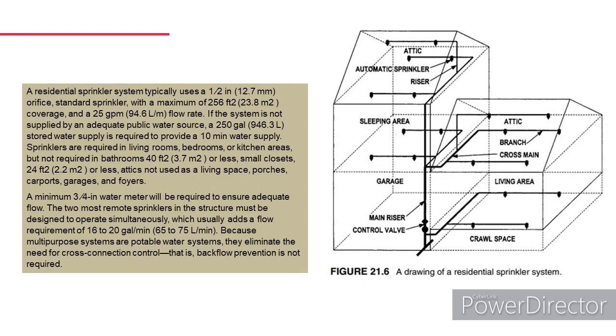A residential sprinkler system typically uses a 1/2 in, 12.7 mm, orifice, standard sprinkler, with a maximum of 256 square feet, 23.8 square meters, coverage, and a 25 GPM, 94.6 L/m, flow rate. If the system is not supplied by an adequate public water source, a 250 gal, 946.3 L, stored water supply is required to provide a 10 minutes water supply.